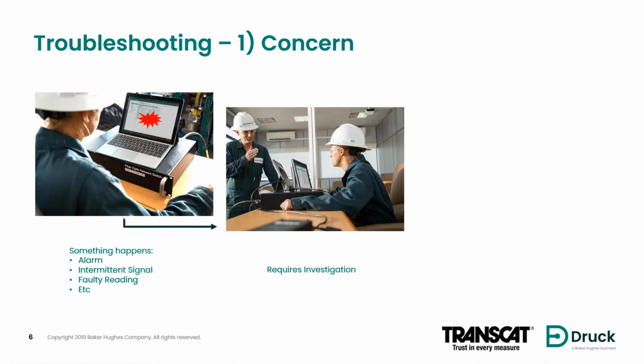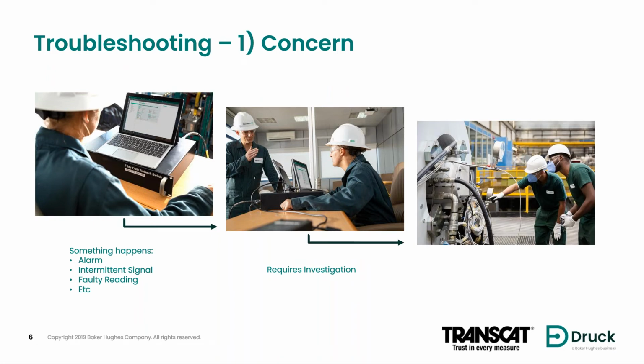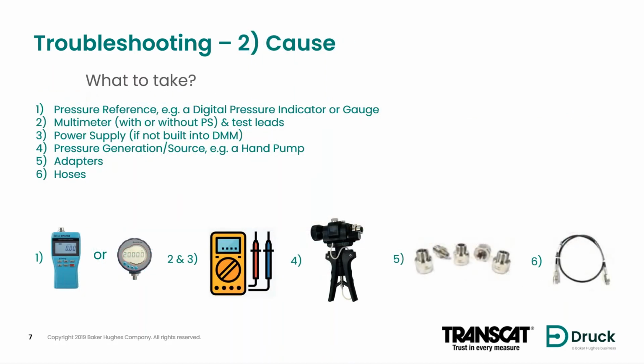And then what happens? Of course, you, the technician, or a technician gets called into the manager's office and says, hey, we have got a problem. I need you to go check it out. Of course, the technician says, no problem, boss, I'm on it. And then we head out to the actual site or location to start our investigation in determining root cause. So that's where we come to our portable pressure calibrator, because what do we take? We have to take something out there to be able to check it and test it.